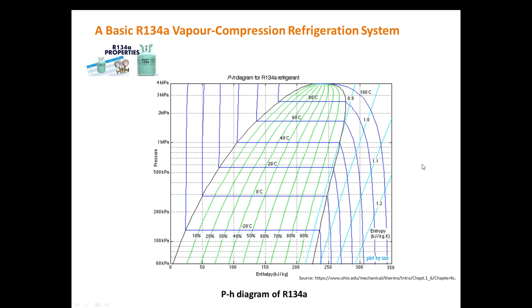Now, analysis of the VCR cycle, that is the vapor compression refrigeration cycle discussed at the beginning of this presentation. To analyze this cycle, five parameters are widely used in the industry: COP (coefficient of performance), EER (energy efficiency ratio), SEER (seasonal energy efficiency ratio), IPLV (integrated part load value), and NPLV (net part load value). We'll see each one by one.